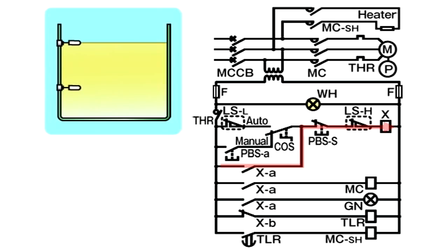If pump operation continues, the fuel oil level rises. The L-S-H float rises and the L-S-H relay turns off. When the L-S-H relay is turned off, current passing through X-A, P-B-S-B, L-S-H, and to X is cut off, and the X-coil is demagnetised. As a result, X-A turns off and X does not remain in self-holding state.